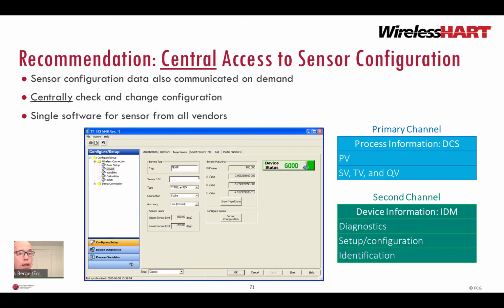So be careful. WirelessHART solves this as sensor configuration is also communicated by request response or client-server communication as a non-real-time second channel. So you can read and write data such as sensor configuration on demand. As a result, this enables you to centrally check and change configuration. Existing IDM software centrally stores the configuration of all instrumentation, including wireless sensors. So the sensor configuration can easily be downloaded into a new sensor at the click of a button when an old sensor is replaced.